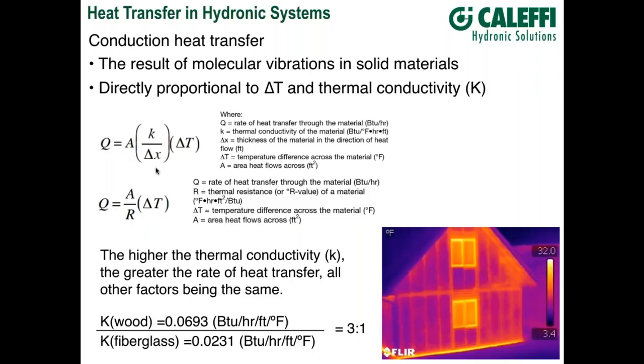You can see the studs appear as a brighter, redder color compared to the purple color between the studs — because they conduct heat better to the outside. The outside surface temperature of the wall is actually higher where there's a stud compared to where there's an insulating batt. The thermal conductivity of wood is about three times that of fiberglass insulation, and that shows up clearly in the infrared thermogram.